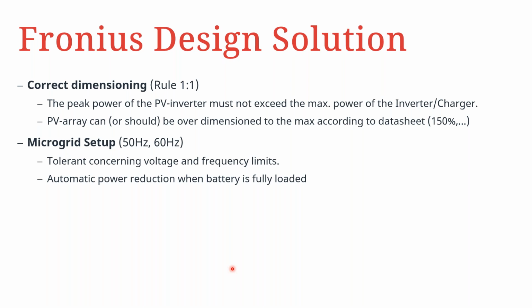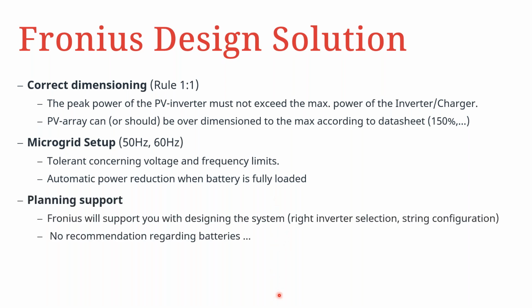As mentioned already, with this kind of country setup or grid setup, you are able to have automatic power reduction when the battery is near fully charged by the Victron inverter. It gives some frequency communication to the Fronius inverter to be able to respond accordingly. In terms of planning and support, Fronius will support you with the design of the system. This includes the selection of the right inverters and the right string configuration, but the recommendations regarding the battery size will not be given by Fronius. This will be given by Victron.